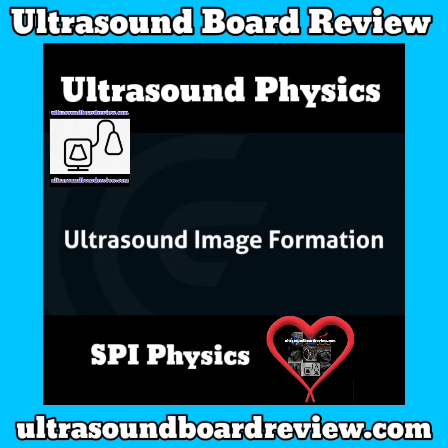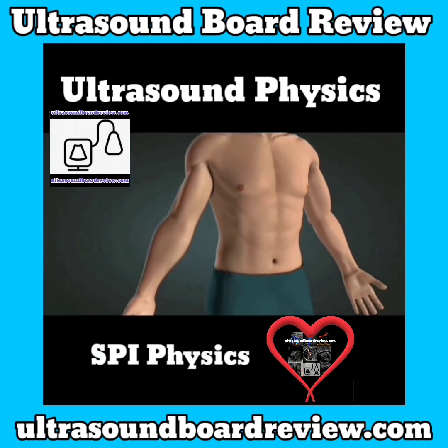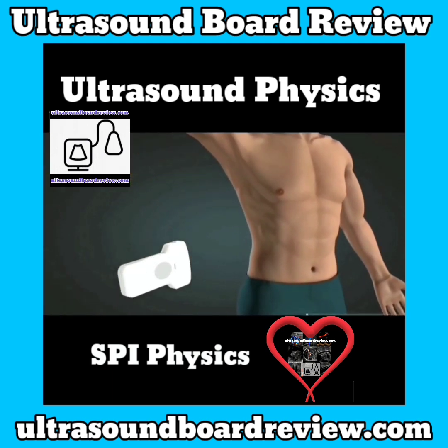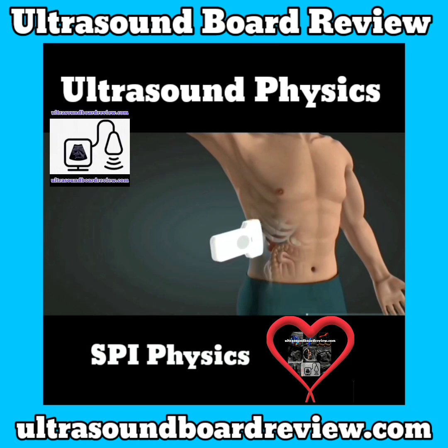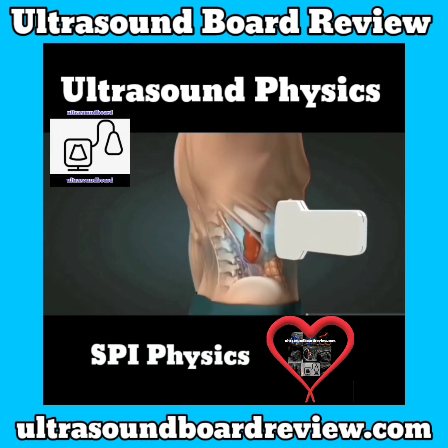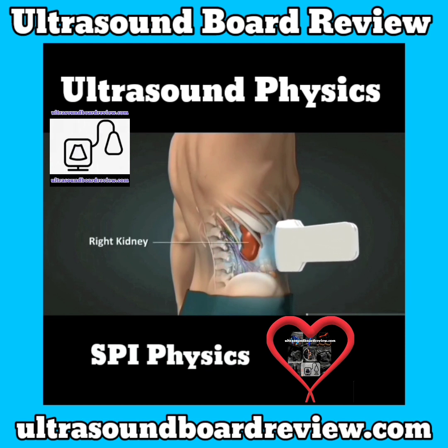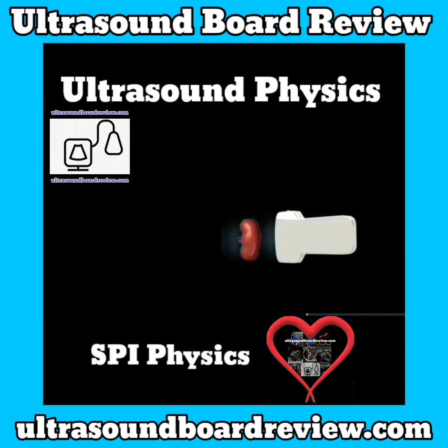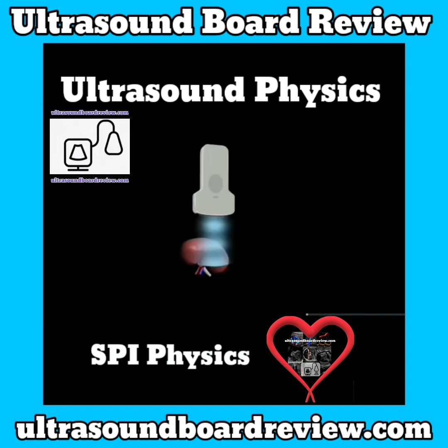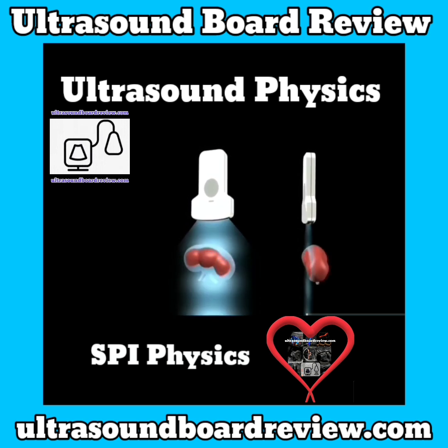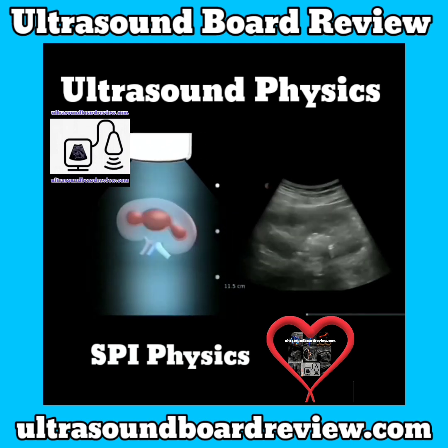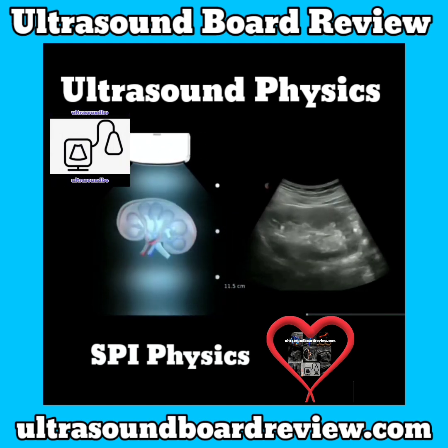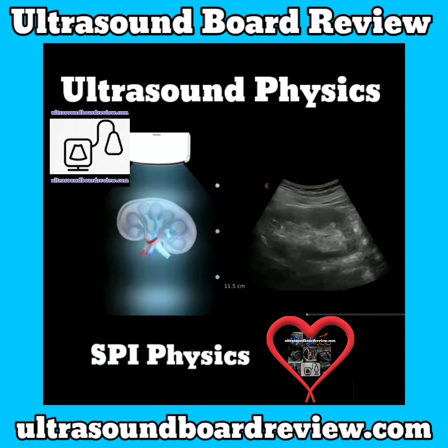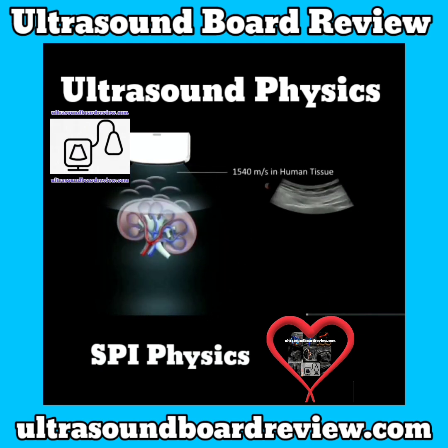An ultrasound image is a cross-section inside the patient that is formed line by line in front of the transducer. Here, we see how a typical image of the right kidney would appear on screen as the user positions the transducer at different angles. To produce images, an electric current is applied to the elements in the transducer. This generates a transmitted pulse, or a sound wave, propagating through the patient. The sound travels rapidly through human tissue at approximately 1,540 meters per second.